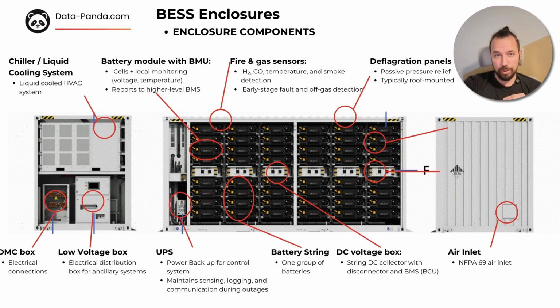Next, we have the low voltage distribution box, where we have all auxiliary system connections, and that helps provide power to communication, to BMS, and UPS. It could be on the back or somewhere around, and UPS provides the power backup for all these sensors and BMS for some time if the enclosure does not have power.